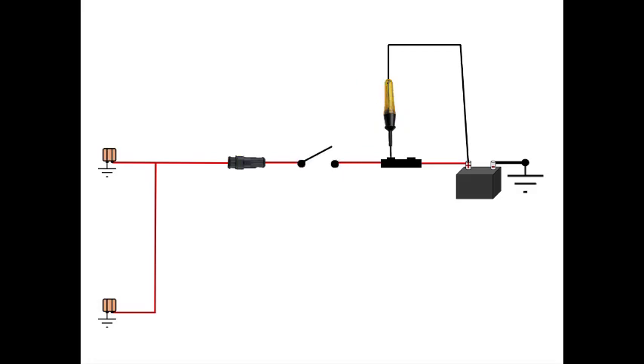The next step would be to close the switch again and find another place to open the circuit beyond the switch. Since there is a terminal connector, it would make sense to unplug it to further isolate the next section of circuit. If after unplugging the connector the light stays on, this confirms that the short is between the switch and the connector.